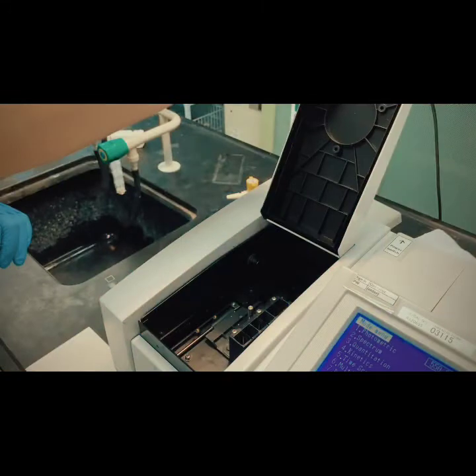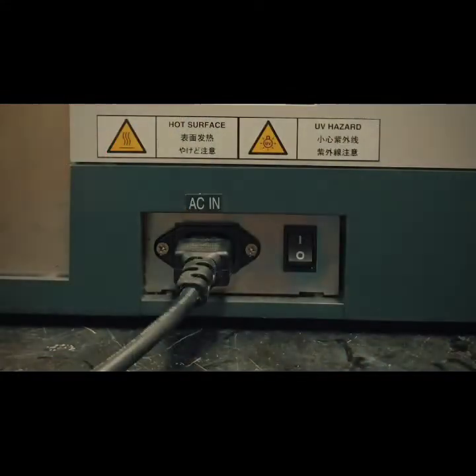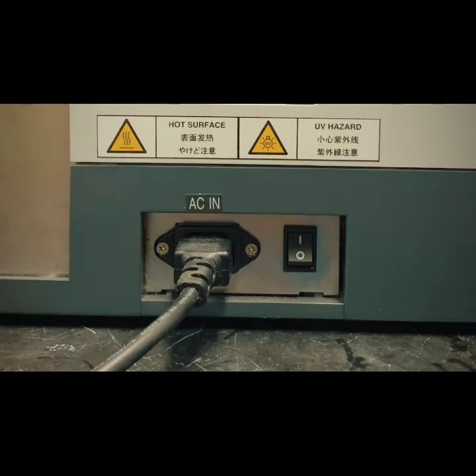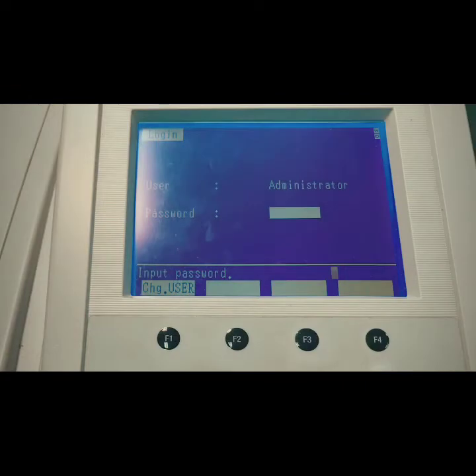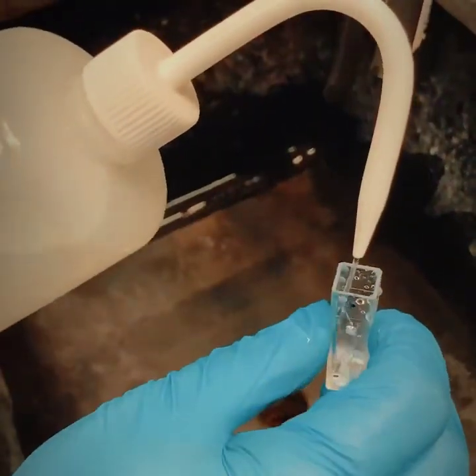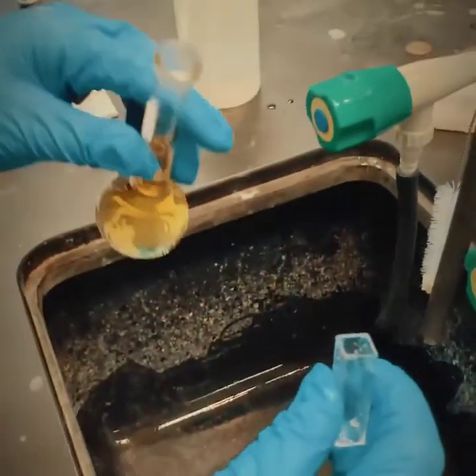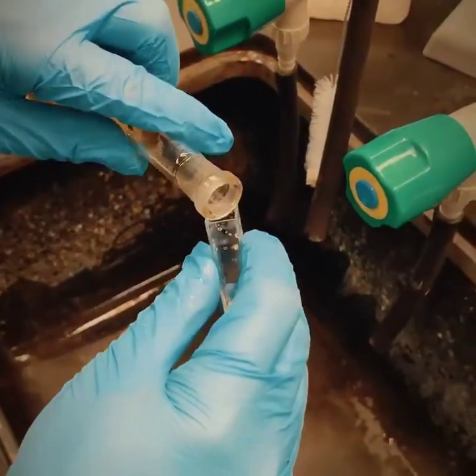Before turning on the machine, ensure that there are no cuvettes in the sample compartment. Turn on the main switch and the power switch, located at the back of each unit. Wait for the machine to run the startup sequence and do not open the compartments during this time. To prepare the cuvettes, wash the cuvette with deionized water and rinse it with the solution you are about to use for the analysis.